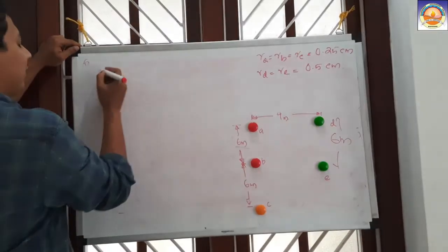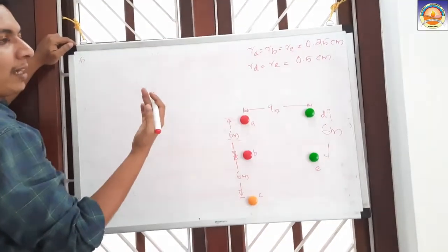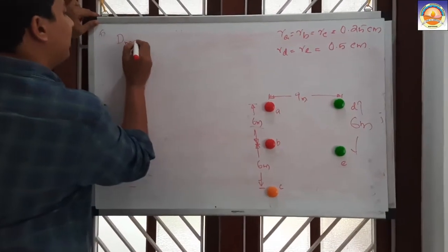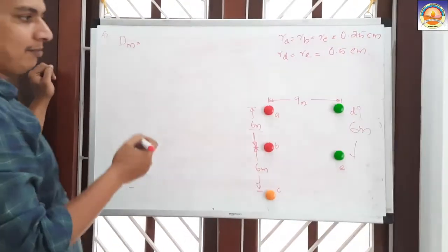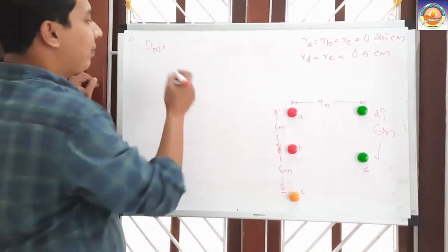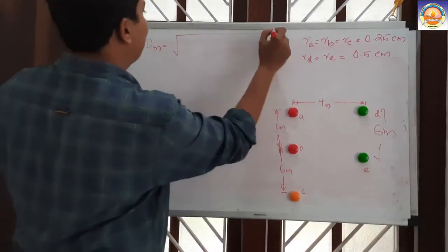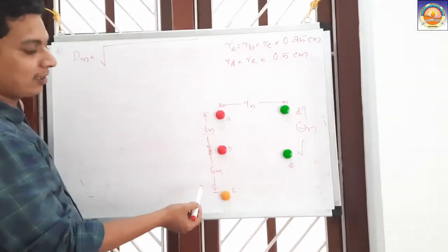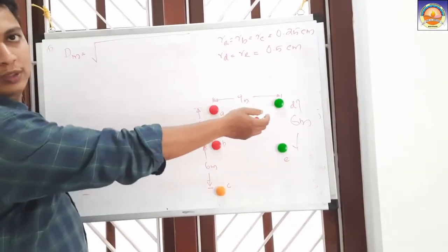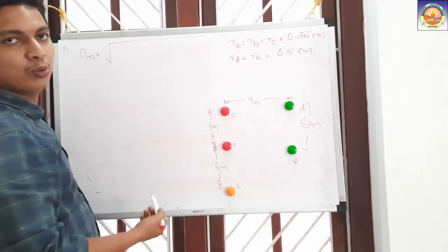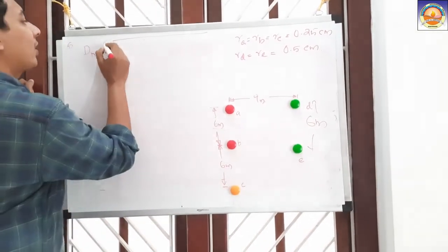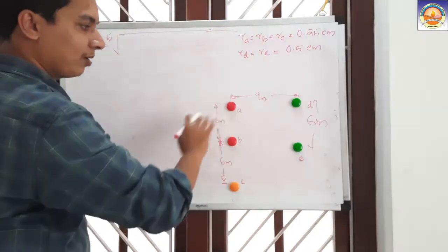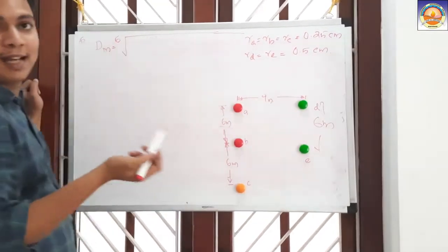The inductance equation is L = 2 × 10⁻⁷ × ln(D_m / D_s). Let us find the GMD (D_m). How many combinations will there be? It is an m-th root, where m = 3 × 2 = 6. So it will be the 6th root of the mutual distances.